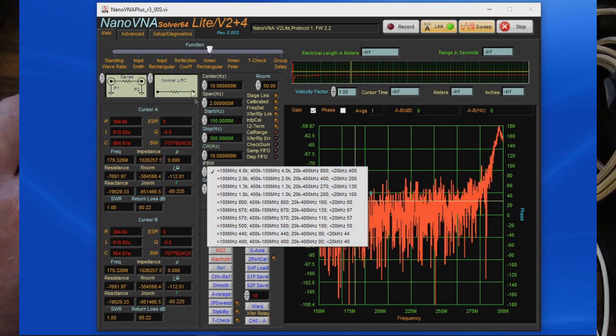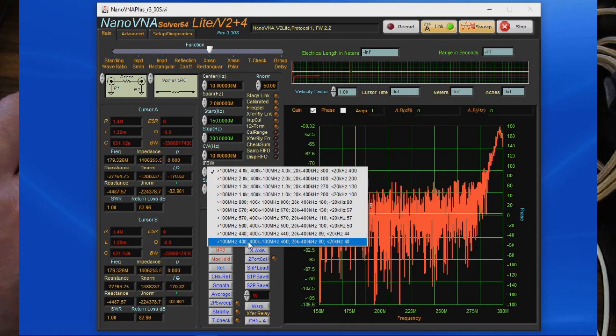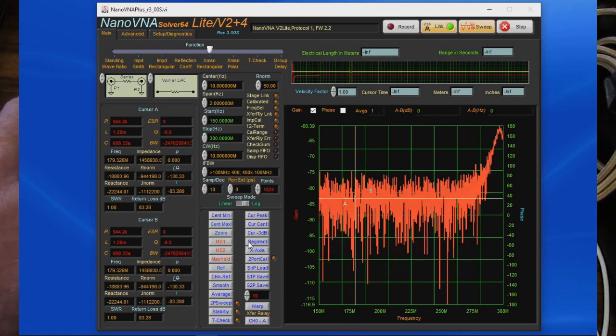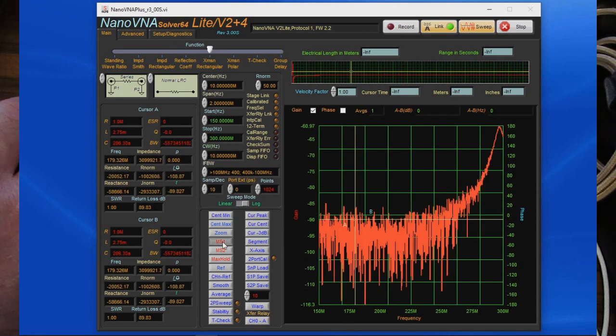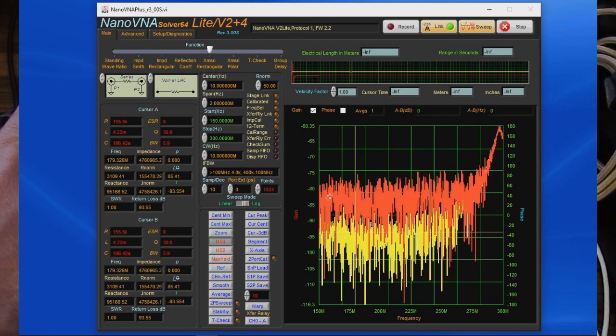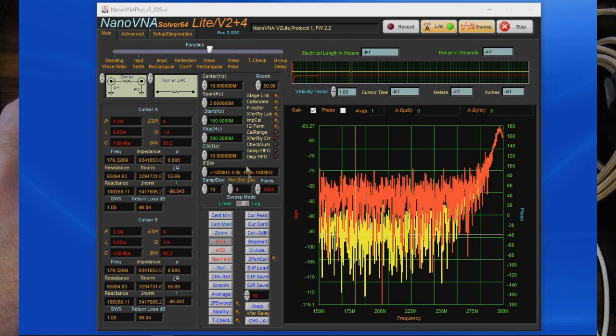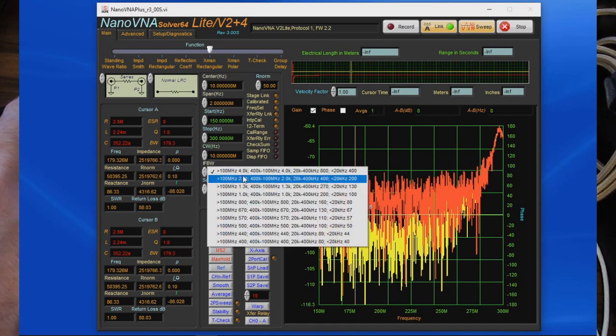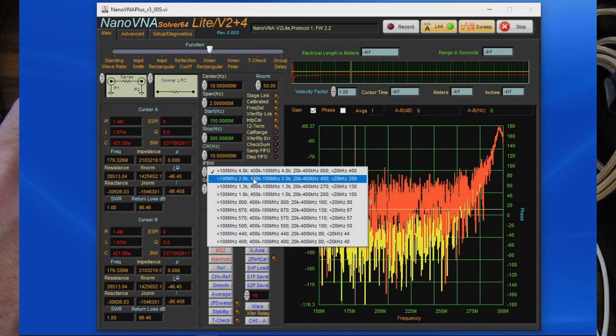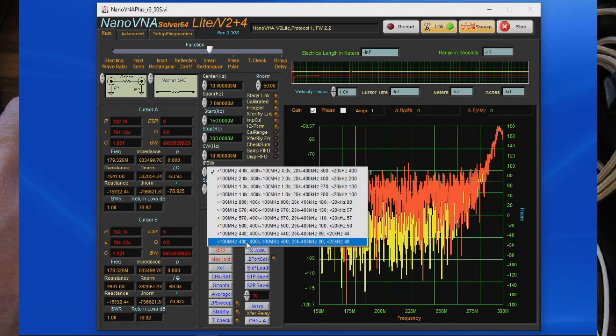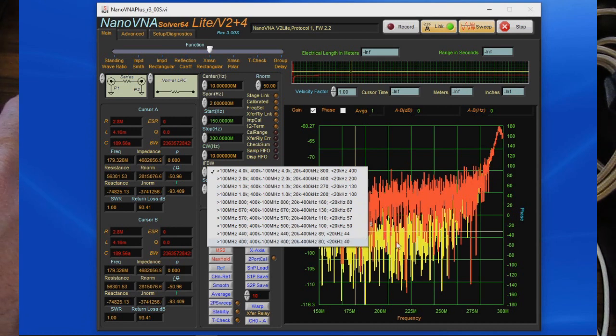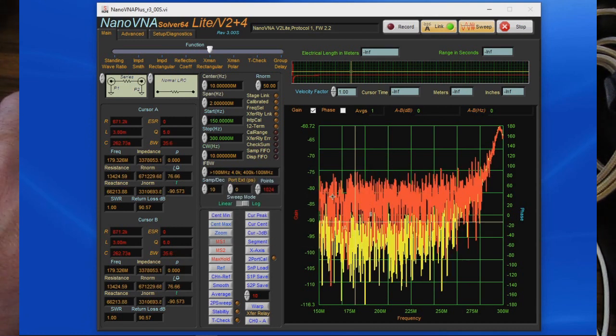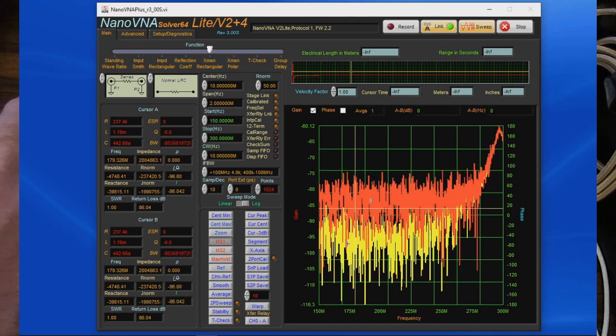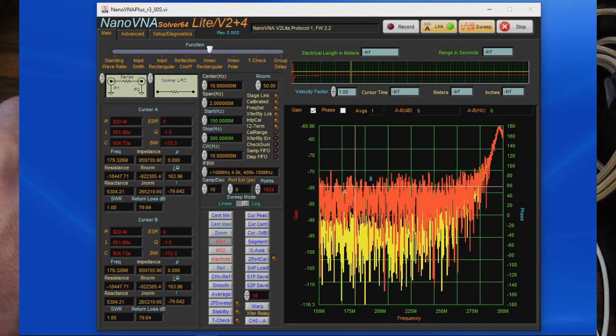So if we want to tighten this down, we can just select it here. This would be 10 averages. Let's go ahead and we'll select store. And now let's change that back. And you can see, just looking at the menu here, we're sweeping, of course, above 100 megahertz. So we've changed the IF bandwidth from 4 kilohertz down to 400 hertz. That should provide us with roughly a 10 dB decrease in noise. And you can see we're pretty close to that.